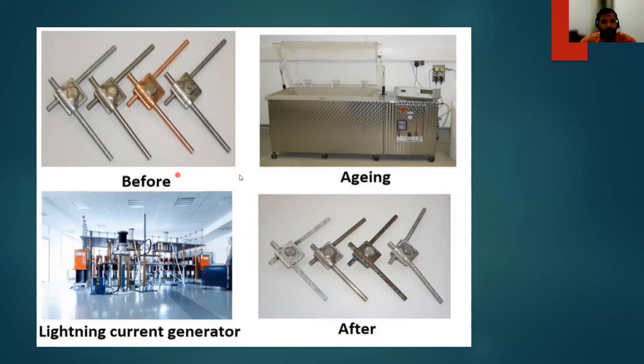What will happen after aging test is done? See, you can feel every material is corroded except the stainless steel. It is lightly corroded. If you want your earthing system for long run, you have to choose stainless steel material.